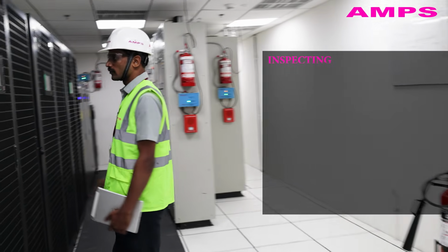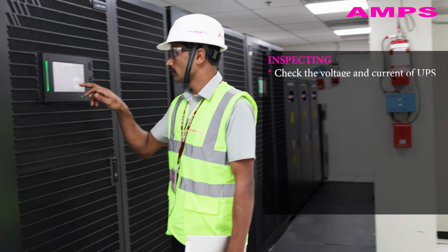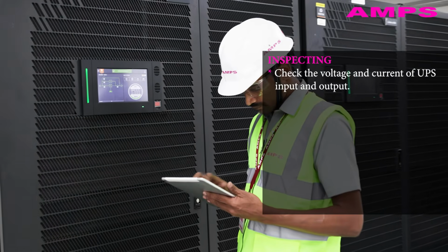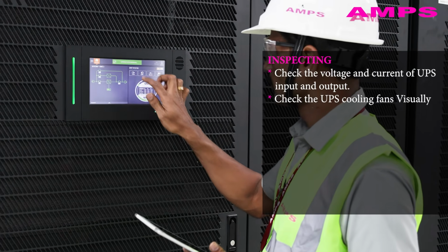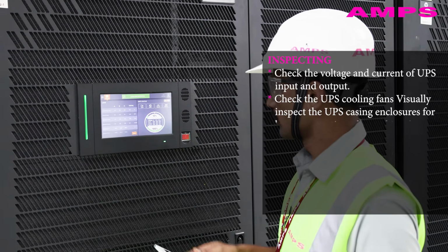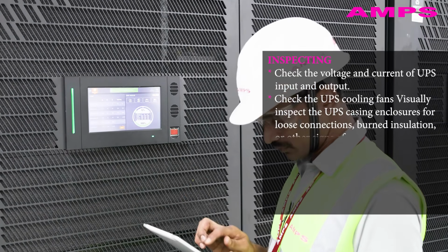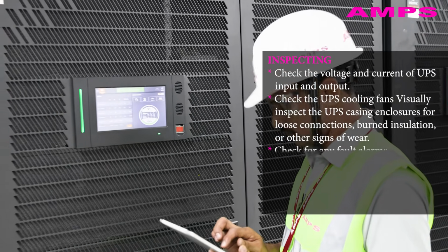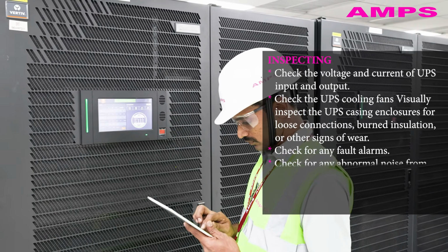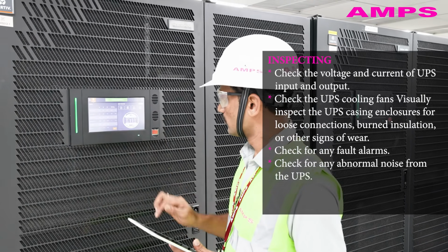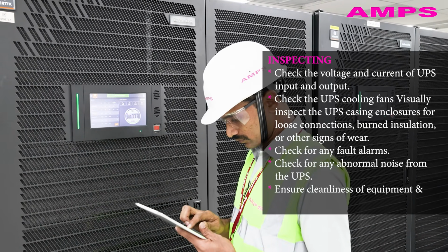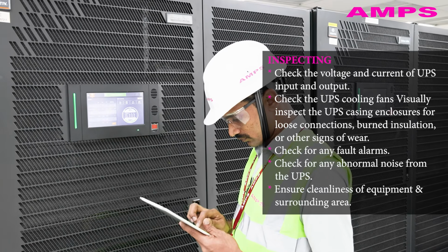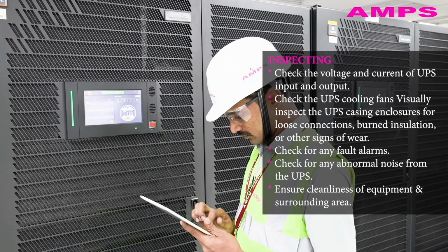Inspecting. Check the voltage and current of UPS input and output. Check the UPS cooling fans. Visually inspect the UPS casing enclosures for loose connections, burned insulation, or other signs of wear. Check for any fault alarms. Check for any abnormal noise from the UPS. Ensure cleanliness of equipment and surrounding area.